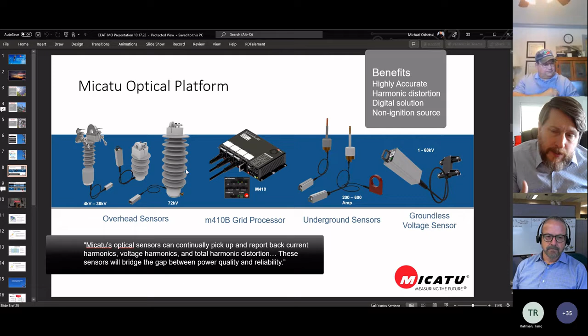We use something called the Pockels effect and Faraday. The Pockels effect is essentially when you take an electro-optical crystal and apply a field to it, it changes the phase of the light. By putting together the system we have, we're able to measure not only the electrical field, but the phase angles, frequencies, and harmonics all in one. Additionally, we measure DC offset, and you're able to give a multi-pronged measurement using a single sensor across multiple voltage classes.